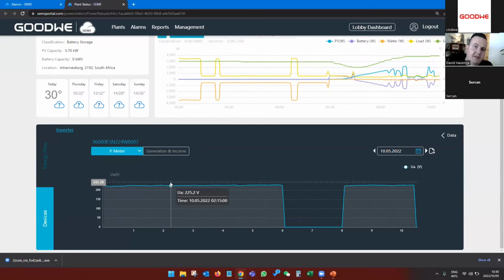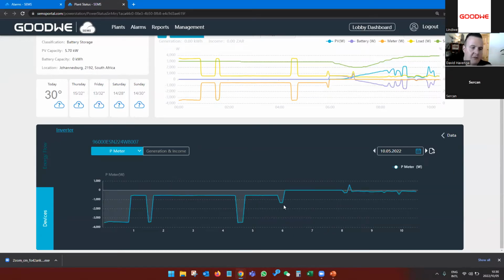Single phase is much easier. 3-phase also, we have individual breakdown, P meter 1, P meter 2, P meter 3. So we can view the individual phase data. Here we can see at night, no battery discharge. Everything is below the line, so it means we are consuming power. So then our meter installation is correct.